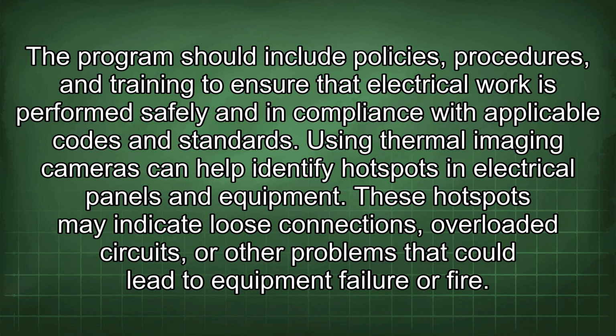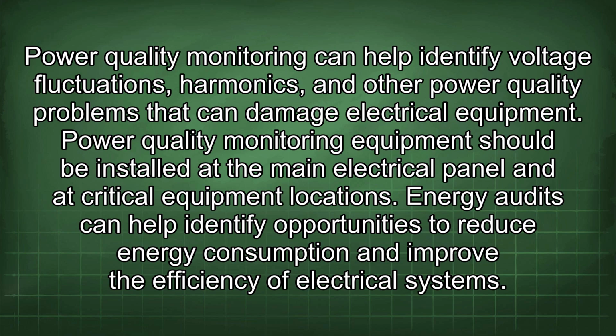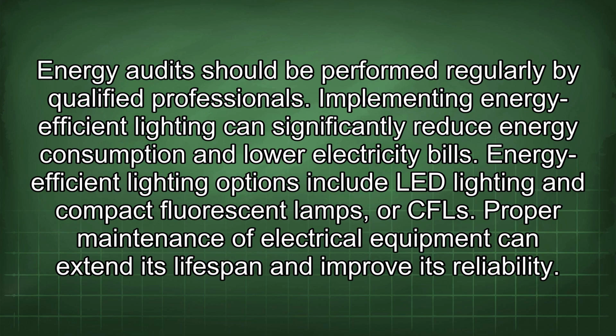These hotspots may indicate loose connections, overloaded circuits, or other problems that could lead to equipment failure or fire. Power quality monitoring can help identify voltage fluctuations, harmonics, and other power quality problems that can damage electrical equipment. Power quality monitoring equipment should be installed at the main electrical panel and at critical equipment locations. Energy audits can help identify opportunities to reduce energy consumption and improve the efficiency of electrical systems. Energy audits should be performed regularly by qualified professionals.